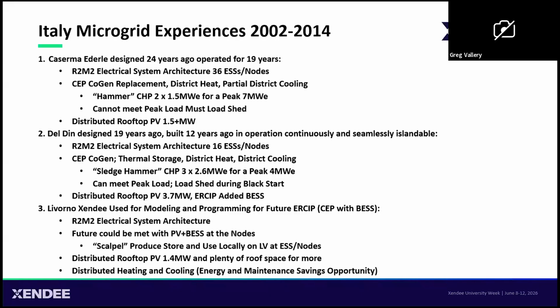The initial idea of making a microgrid was when we combined heat and power into an existing older central heating plant. In the end, we used an ESPC and put in two 1.5 megawatt diesel engines. The total load on the installation is around 7 megawatts, so I like to call this the hammer approach - the engines were big enough to support all the critical loads, but they could not meet the peak load, since we only had 3 megawatts of electricity. Ultimately, we did the ESPC portion, but then we came back and did the actual control portion that enabled those engines to become power for the microgrid.